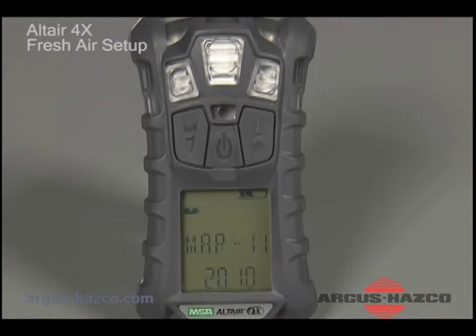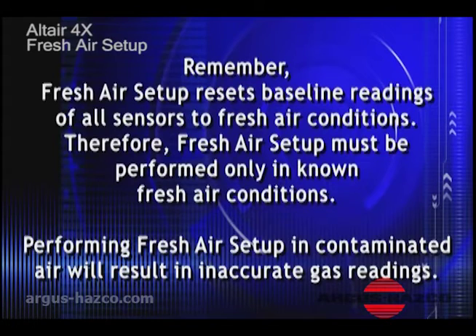In addition to the Fresh Air Setup prompt that occurs during startup sequence, users may elect to perform Fresh Air Setup at any point when the instrument is in measure mode. Remember, a Fresh Air Setup resets baseline readings of all sensors to fresh air conditions. Therefore, Fresh Air Setup must be performed only in known fresh air conditions. Performing Fresh Air Setup in contaminated air will result in inaccurate gas readings.